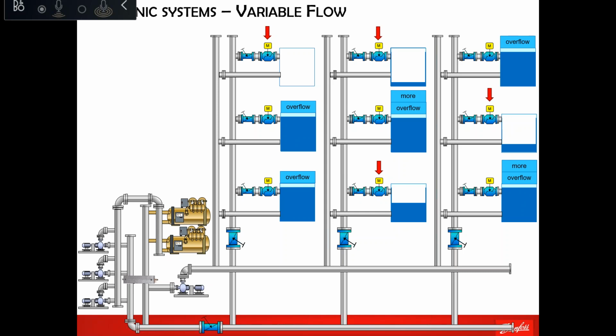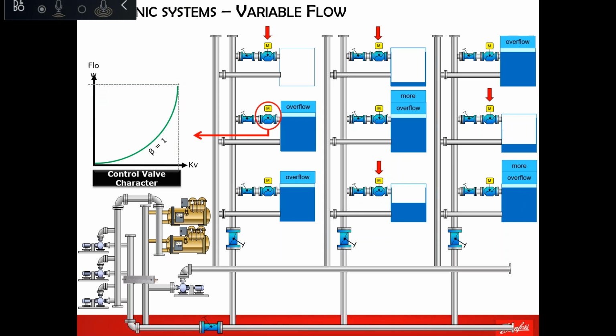If you close one valve, the pressure will move to the next one. Why is that? Because again, we said that it's static balancing. It's not dynamic. There is no automatic response to the pressure change. And if the control valve is changing in pressure difference or dynamic pressure, the authority of the control valve will change as well. And that's what explained that you have a two-way valve with an equal percentage characteristic that will turn into on-off valve. And as you can see here, with an authority of 0.3, you have like 100% wasted range. And with an authority of 0.1, it's 50% on 0.3 and 100% on 0.1. This wasted range, since you are recirculating the same amount of water in your installation, if you have overflow somewhere, it's underflow somewhere else. So this is, in general, variable flow system with the two-way and DRV.